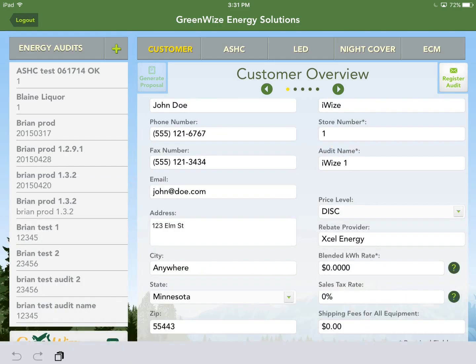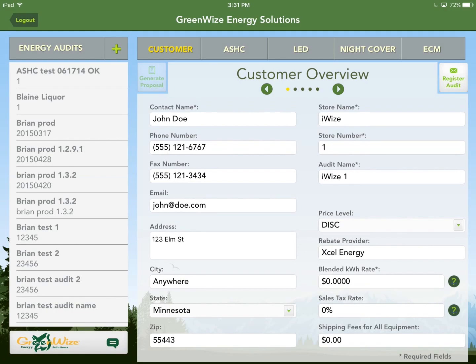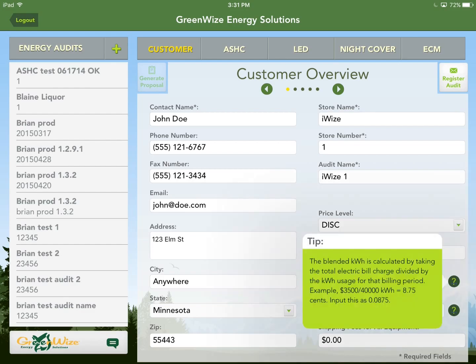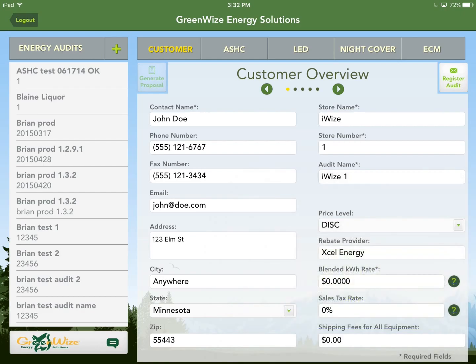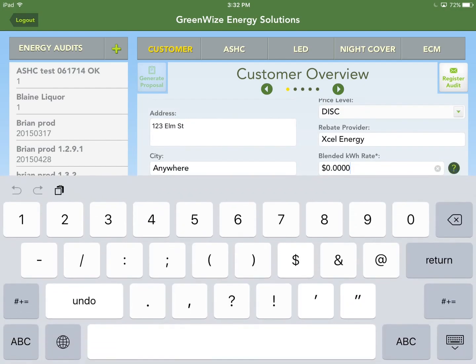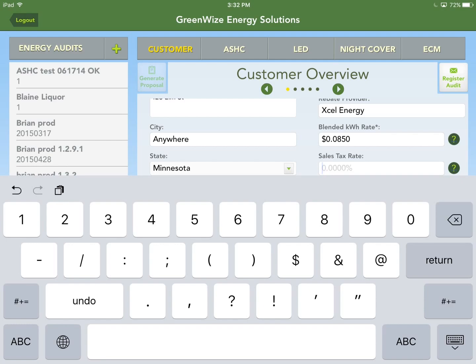The blended kilowatt hour rate is not just the kilowatt hour rate on the electric bill — it's calculated by taking the total electric bill charge divided by the kilowatt hour usage for that billing period. This encompasses the entire bill, including all fees and charges, providing a much more accurate savings calculation. A common rate around here is eight and a half cents. Sales tax rate — we'll do 7.5%.